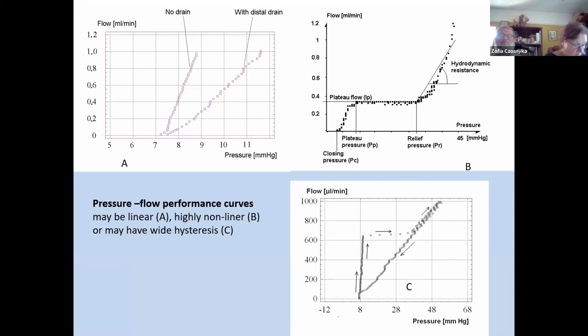It's important to note that most valves are controlling the pressure, as shown here in figure A. This is a plot of pressure against the flow through the valve. The slope of the curve is determined by the hydrodynamic resistance of the device. The connection of the distal drain can significantly increase this resistance. The steeper the slope, the smaller the resistance. Very few devices can control the flow.